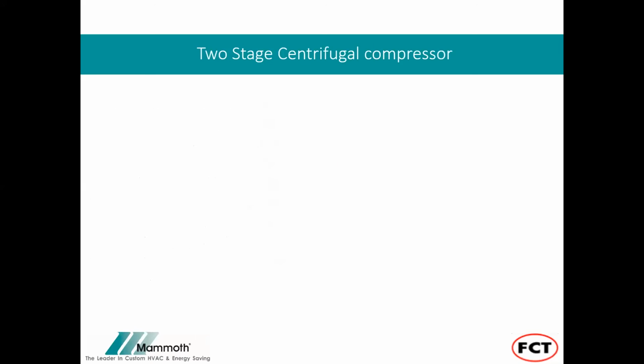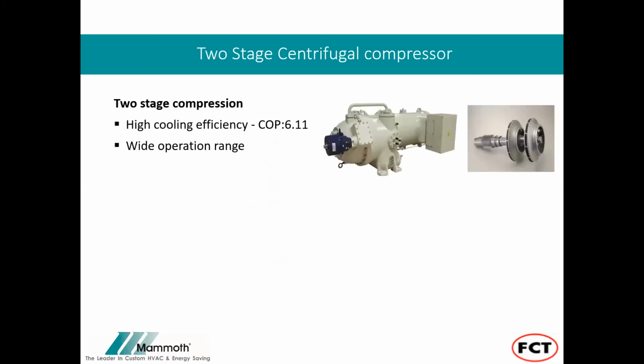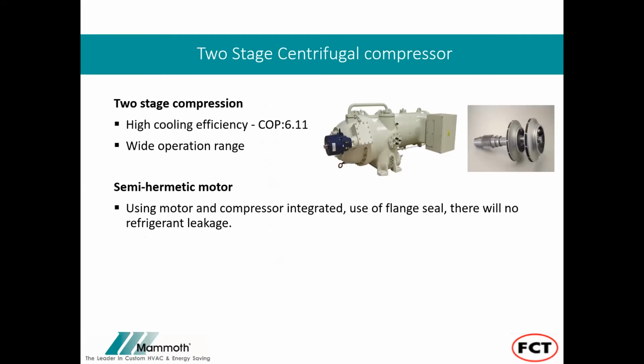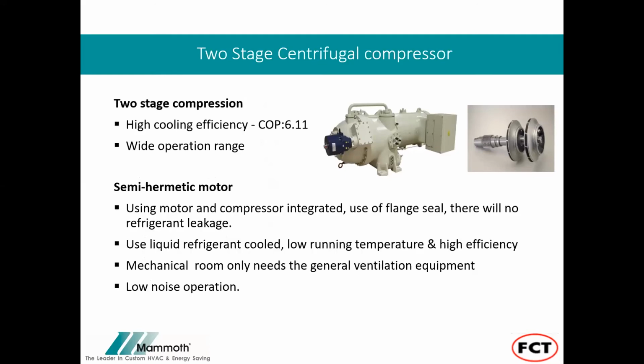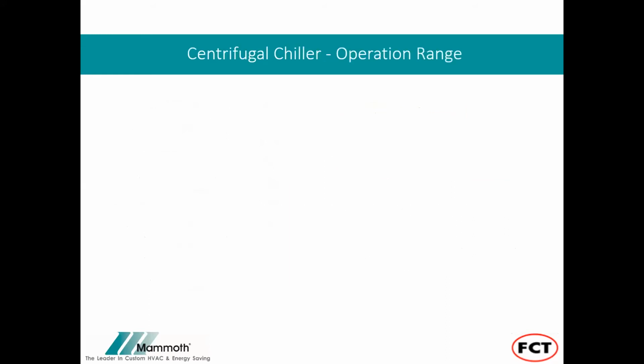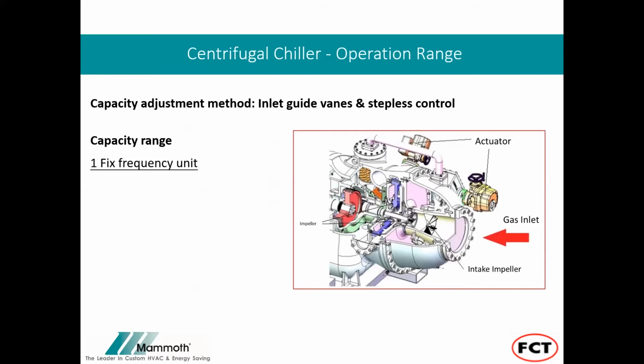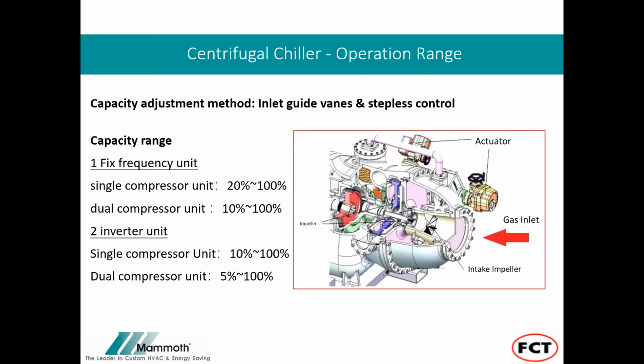Also, going a little deeper into the product itself, we are using a two-stage centrifugal compressor, semi-hermetic motor, and it is liquid refrigerant cooled, low temperature running, and high efficiency. And also it's a low noise operation. In terms of the operational range, we have a full capacity range in the two types, fixed frequency unit and inverter unit. And the capacity control can go as low as 5% to 100%. This is our operation range.